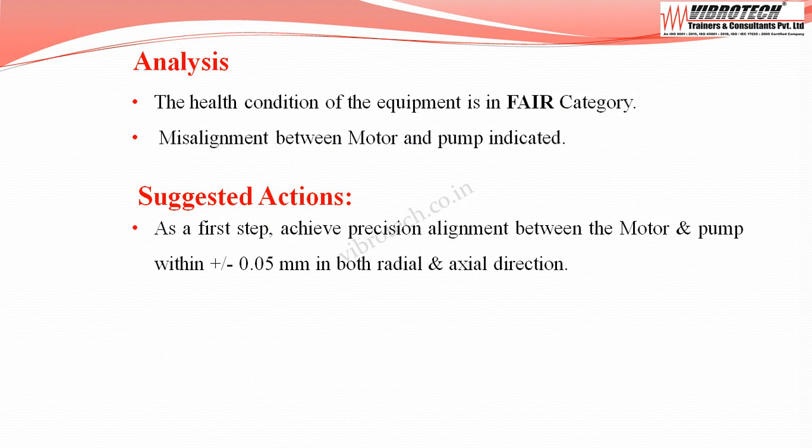As per the analysis, the suggested action is as follows: as a first step, achieve precision alignment between the motor and pump within plus or minus 0.05 mm in both radial and axial directions.